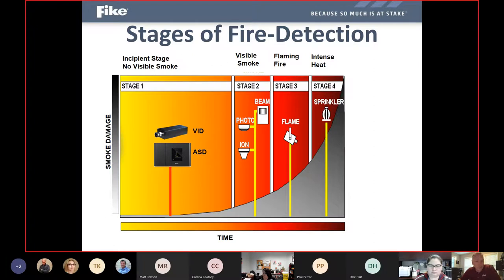You can see that the gray indicates the smoke damage and the buildup of heat in different stages there. And so we've got different areas that we could potentially input detection devices to try to detect something, based on how early on and how much smoke and or heat damage we want to try to avoid by getting that earliest detection. So the first options that we really have in the line there are video imaging detection and air sampling detection by Xtralis VESDA.